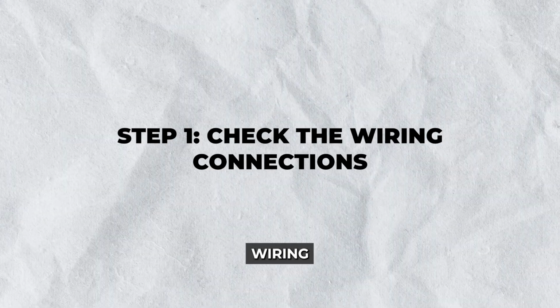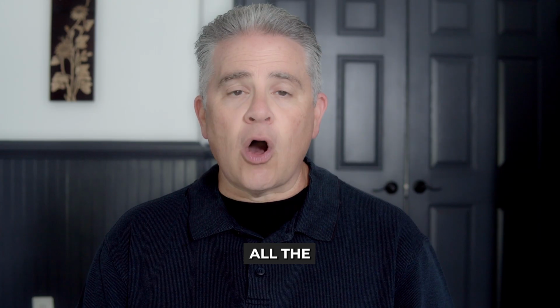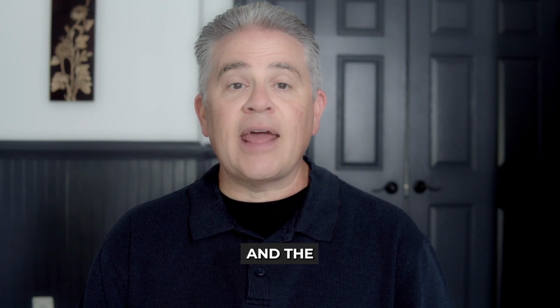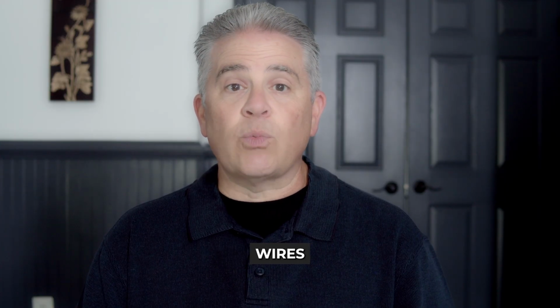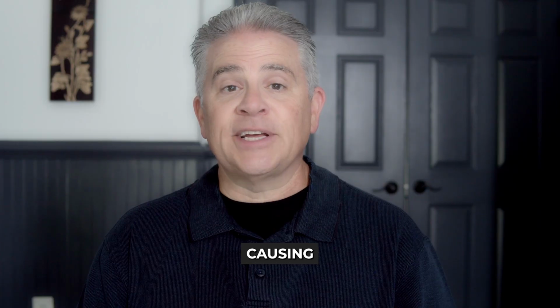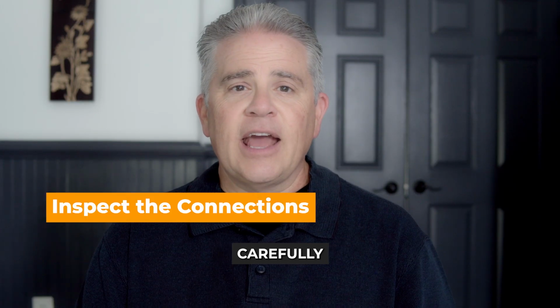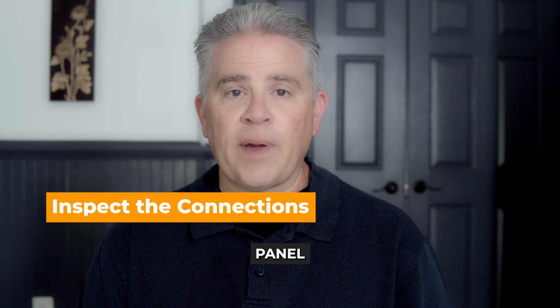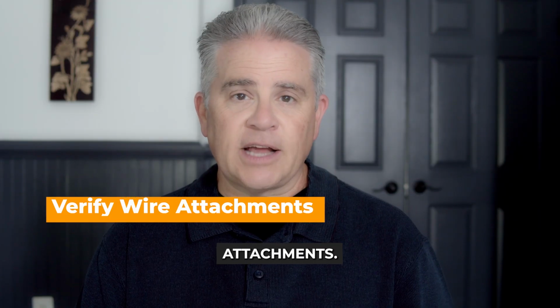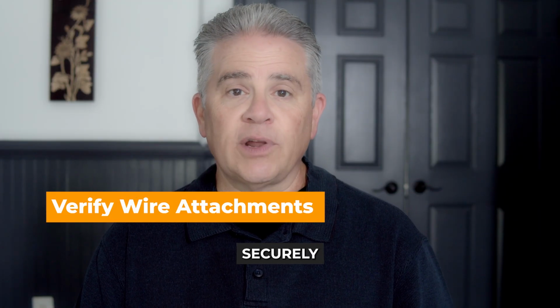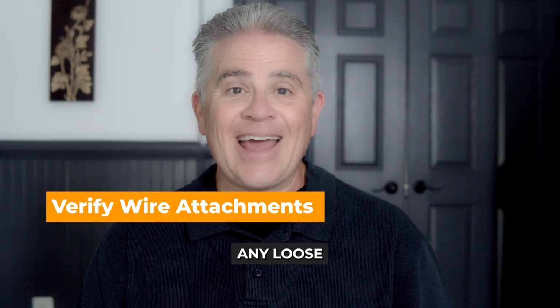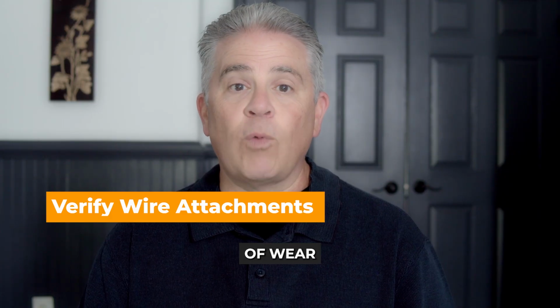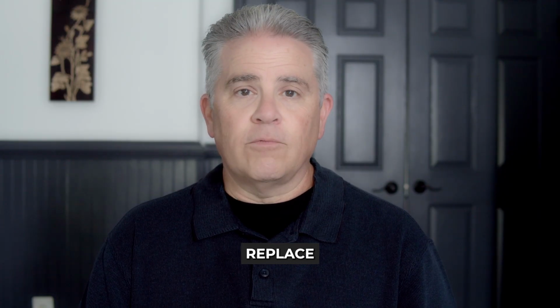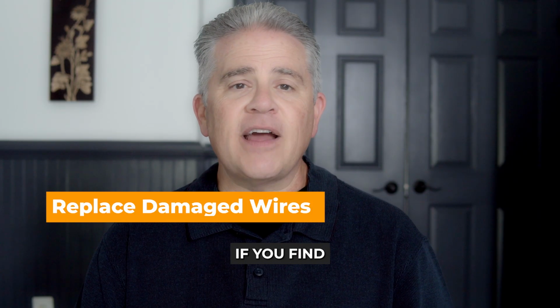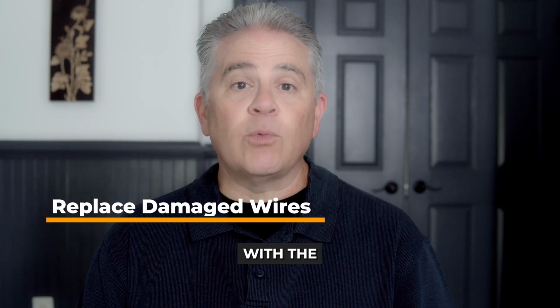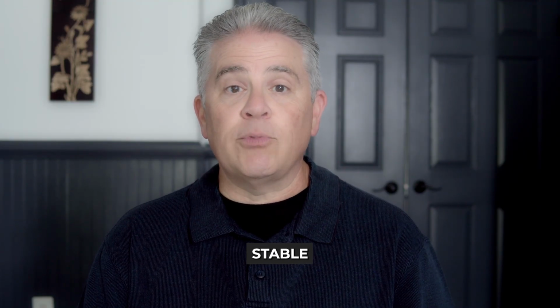Step 1. Check the wiring connection. The first step is to examine all wiring connections between the keypad and the control panel. Loose or damaged wires can disrupt communication, causing an ECP error. Inspect the connections. Carefully open the keypad and control panel covers. Verify wire attachments. Ensure each wire is securely connected to the correct terminals. Tighten any loose connections and check for signs of wear or damage, such as frayed wires. Replace damaged wires. If you find any damaged wiring, replace it with the appropriate gauge wire to ensure stable communication.